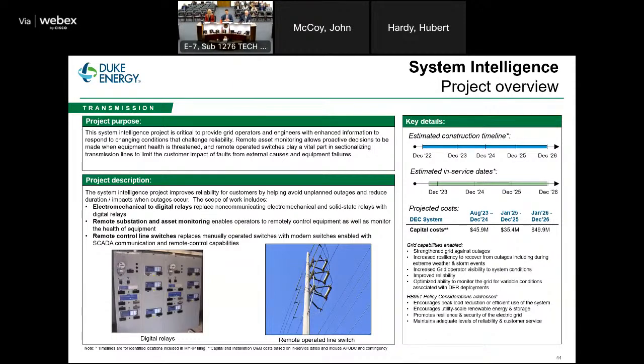So after an outage, we get the information from the relays on where the outage occurred. The operators make the switching decision from the control center, and we're able to either restore partial or sometimes full customer load. That's a significant improvement from the legacy model where all we know is we have breakers that have opened at substations to isolate a problem that occurred on the transmission line.